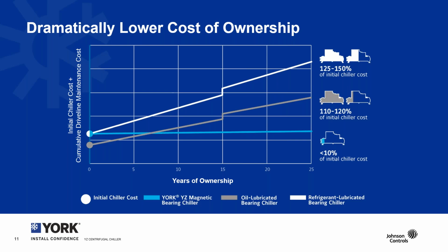Those lines show the cost of regular maintenance, interrupted by a spike from a teardown, inspection, and partial rebuild part of the way through the chiller's life. These lubrication systems create driveline maintenance costing 100 to 150% of the chiller's initial cost. Compare that with a magnetic bearing system, where driveline maintenance is less than 10% of the cost of the chiller.